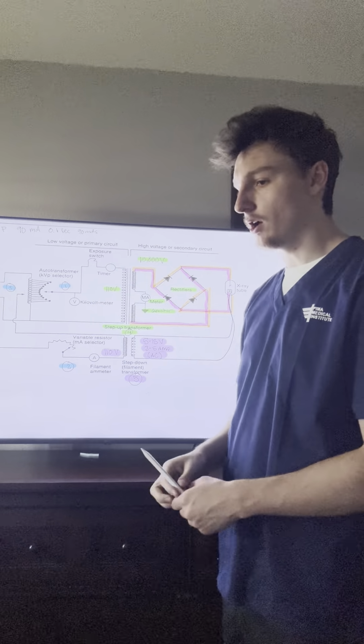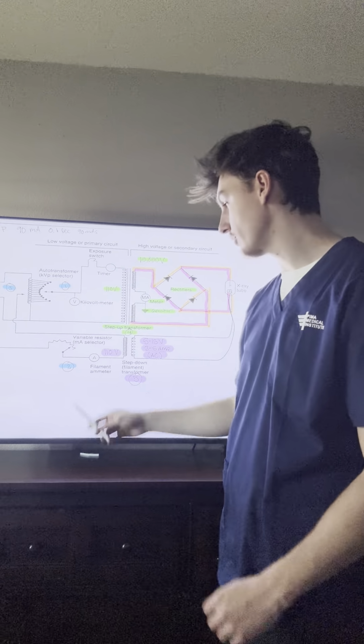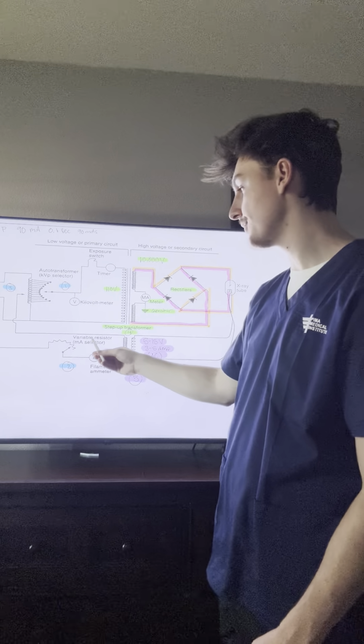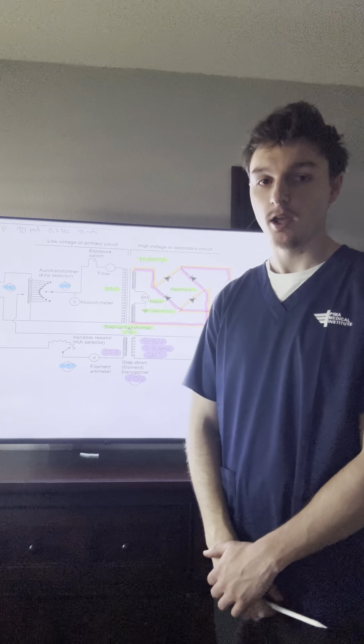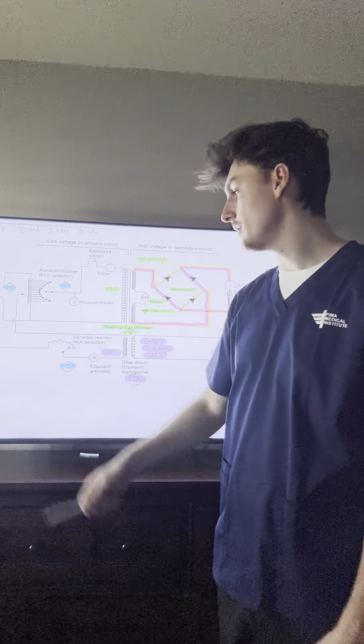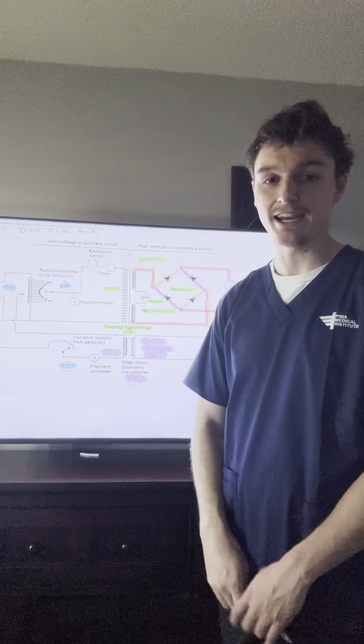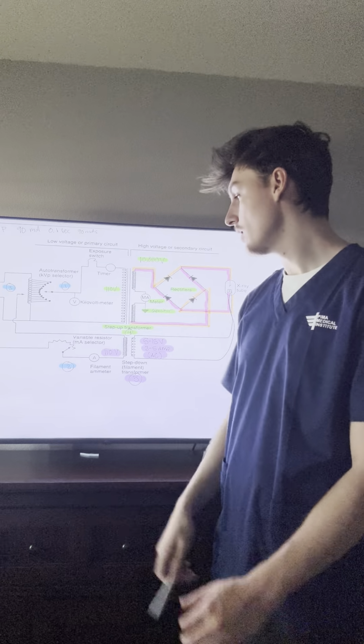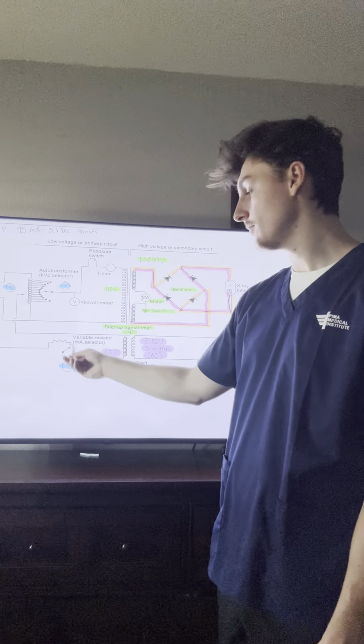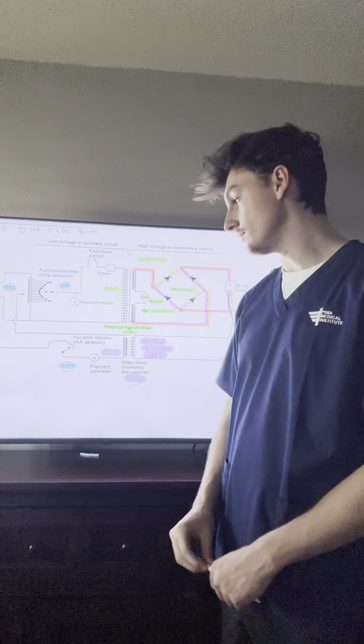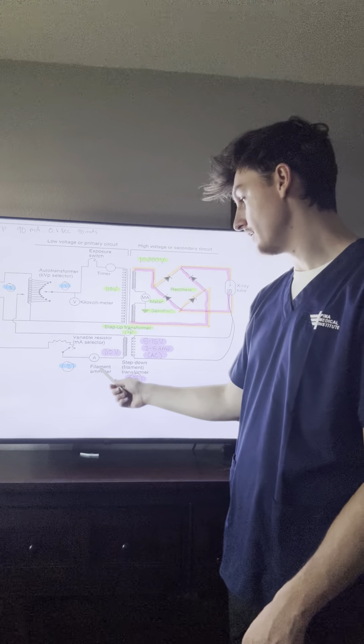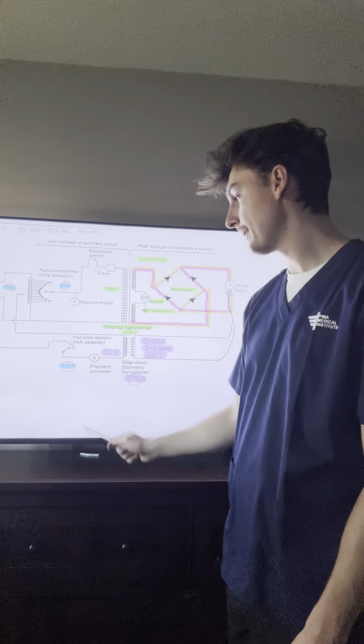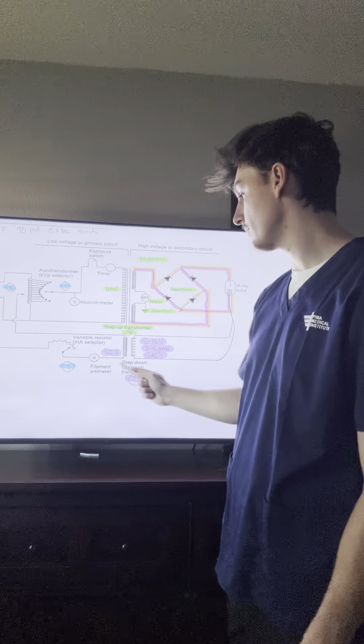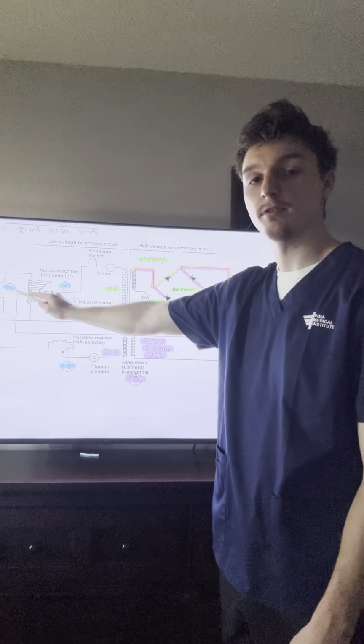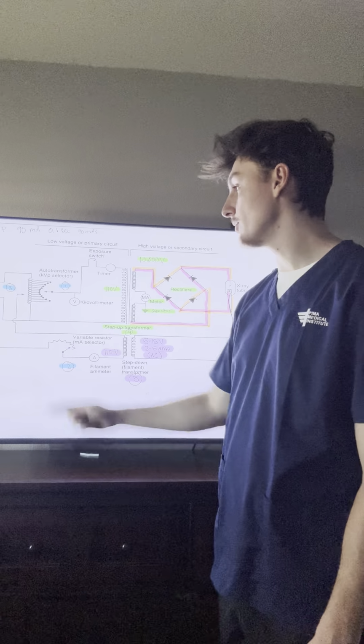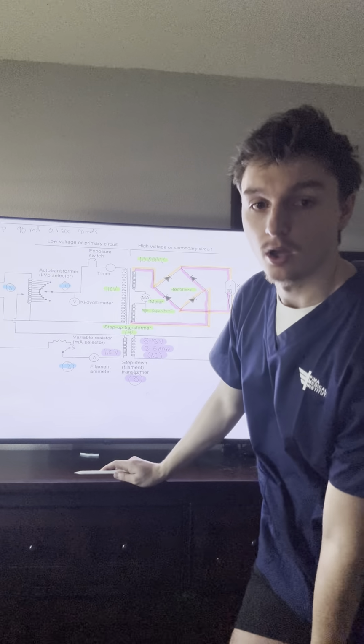Now we can jump down here to our second point of induction, which is going to be our variable resistor, or our mA selector. It's going to be kind of like the kVp selector, but this time it's going to be reading our 90 milliampere, our 90 mA. It's going to use this little hand, and it's going to pick the little setting right there. And it's going to be read by the filament ammeter, which is right here. So now we can follow this line all the way up to our third point of induction over here, which is going to be near our auto transformer.